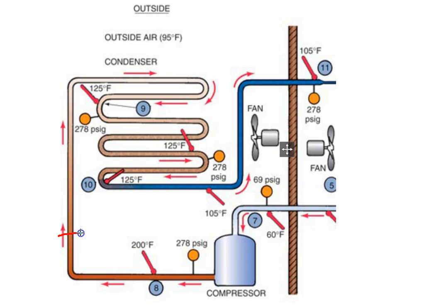So we de-superheat up to this point, then we change state from vapor to liquid through the condenser to this point until it's 100% liquid, and then we're on the subcooling part of the refrigeration cycle. And remember, the PT chart only refers to the change of state part of the refrigeration cycle, which is from just the beginning of the condenser after the de-superheating happens until just about the end of the condenser where the subcooling begins to start. So this is what the PT chart refers to.